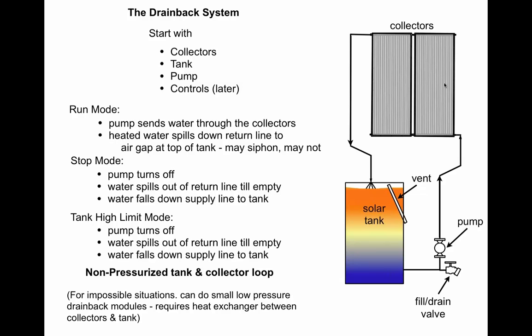We run this system all day long, pumping water through the bottom, spilling back into the tank. At the end of the day, a rain shower, or cloud cover — when we can't gain heat from the collectors — we turn the collector pump off. The water in the return line drains through that air gap at the top, and the rest drains backward through the collectors, through the pump, and back into the tank. If you turn the pump off, the water cannot stay in the collectors. So a power failure is a normal operating mode — you do it every day regardless.